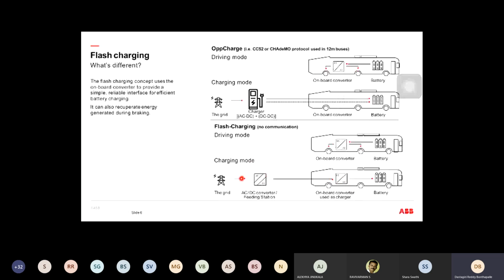Now, my contribution in this is particularly with respect to this rectifier. You need to maintain a constant DC voltage source and meet the grid code. What is the grid code? The percentage THD of voltage, percentage THD of current should be less than 5%. And the DC bus regulation should be maintained at 500 volts, whether the bus is there or not. So generally you choose an IGBT converter.